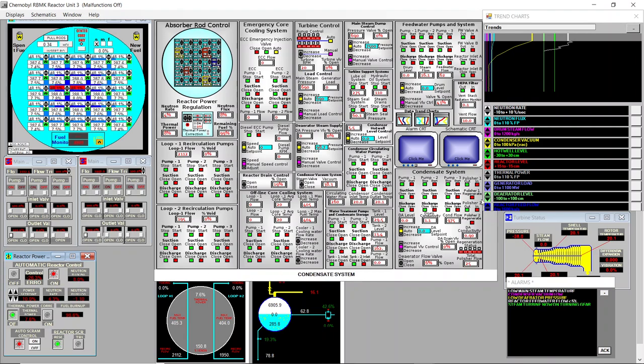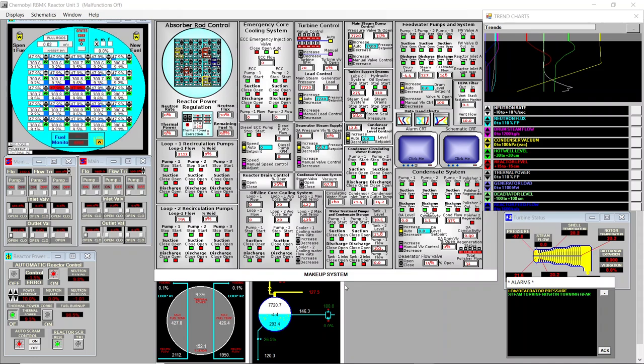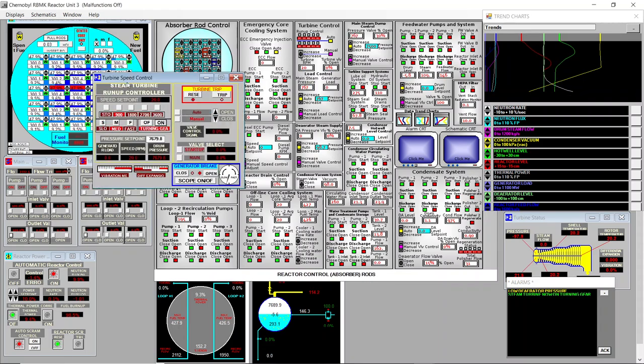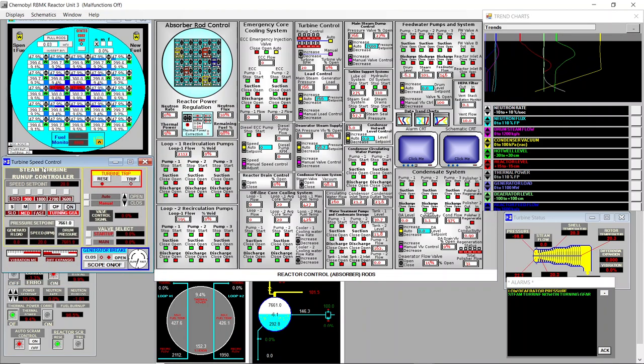Okay, we are now at 10% of power set point. We see how the condenser vacuum increases. And after that, you can continue the normal startup procedure. So everything else is fine. We have a low deaerator pressure. These are normal warnings, I think. Let's see if everything is fine, and I can start spinning the turbine, just to confirm that this fixes the low condenser vacuum issue.